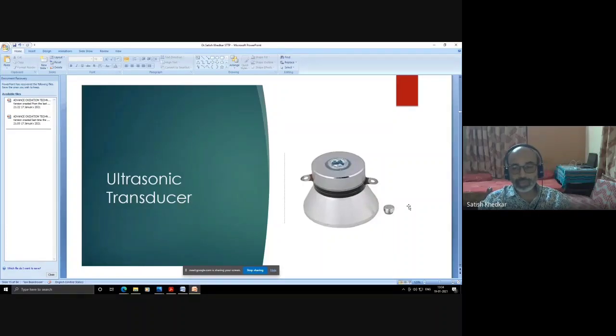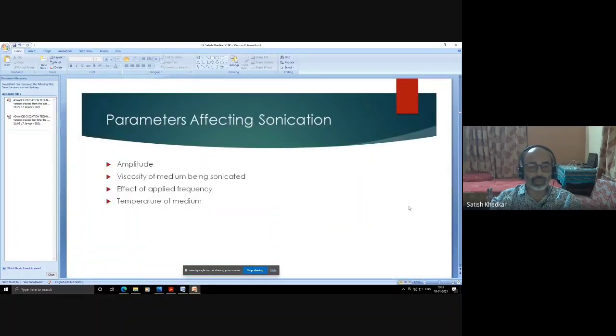So as far as possible, the load should be checked, and it should be ensured that excess load is not there on the machine. Otherwise the transducer may blow off because of excess load. So proper care should be taken while cavitating the liquid. You should also make sure the temperature probe is inserted into the liquid, and that it is not a flammable liquid, because high temperatures are generated during cavitation because of the implosion of microbubbles in the liquid being cavitated.